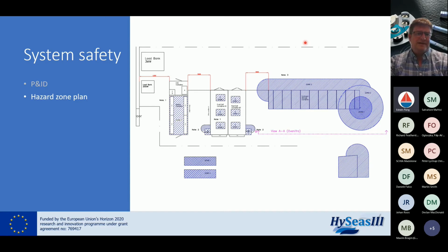We started early with the hazard zone plan together with the land requirements for hydrogen storage, distance towards buildings and so on. This shows the hazard zones, zone 1 and 2, around the hydrogen storage, and the ventilation from the container. This is the fuel cells, and it's only a hazard zone inside the fuel cells - it's not supposed to be able to leak, but Ballard will say more about that.